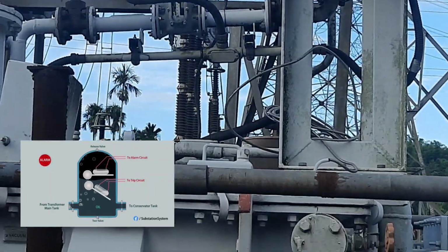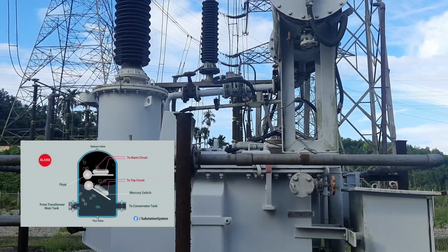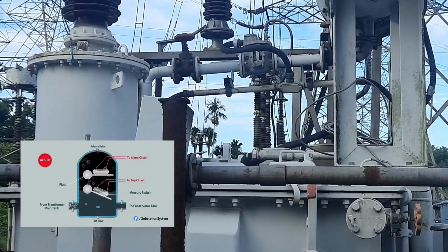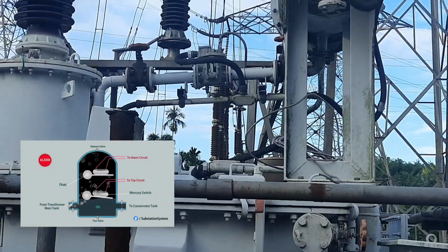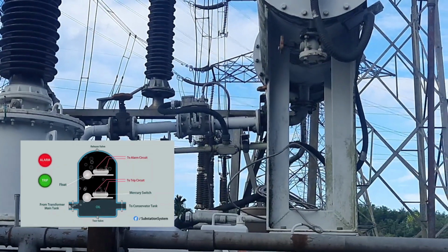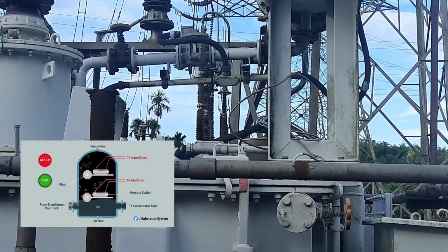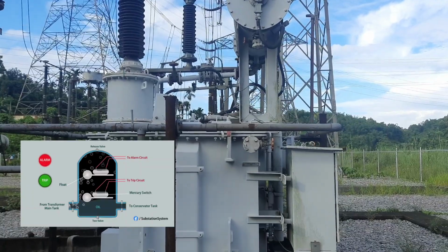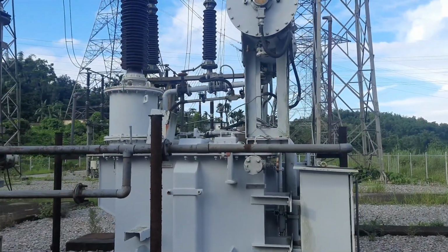And if the fault continues or the fault is severe, then the air will keep pushing the oil down, and a point will be reached where the second float, which is at a lower level, will also be actuated, giving you tripping signals to the breaker, and the breaker will disconnect the reactor or the line, in fact.